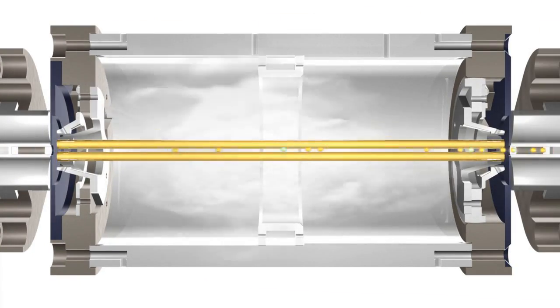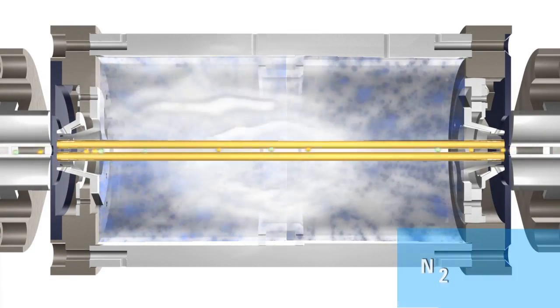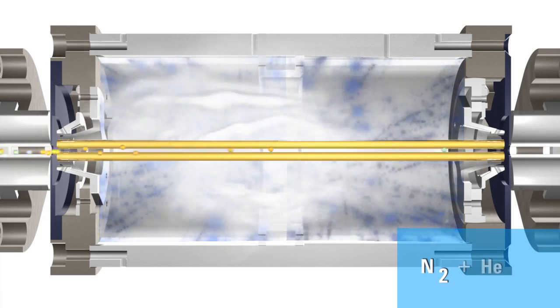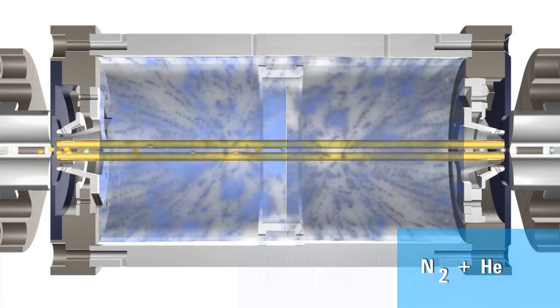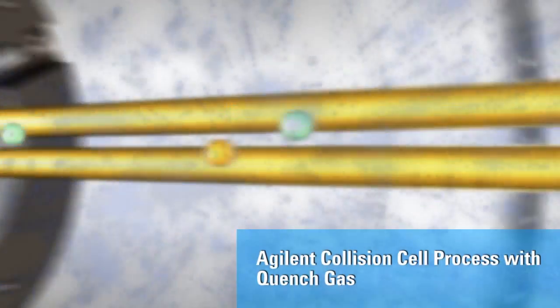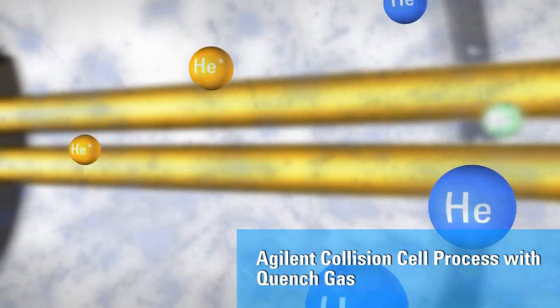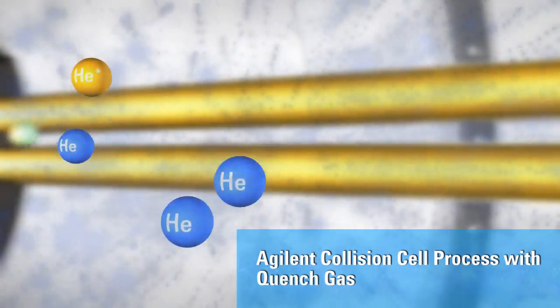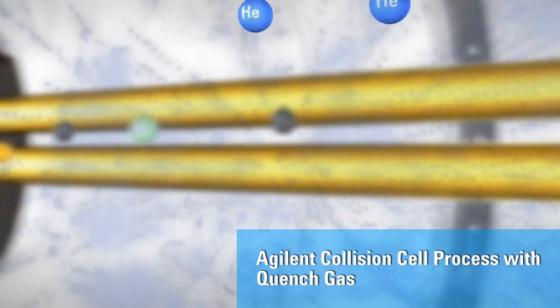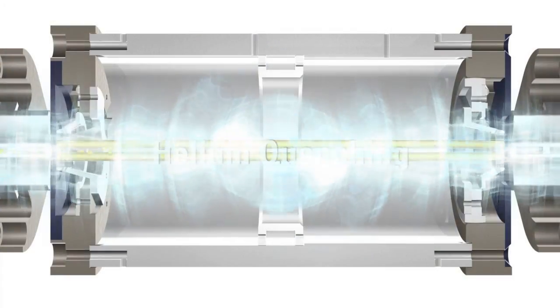During the development of the 7000A, Agilent engineers realized a small flow of helium added to the nitrogen collision gas was a very effective way to reduce the transmission of metastable helium through the collision cell. We call this patent-pending solution helium quenching.